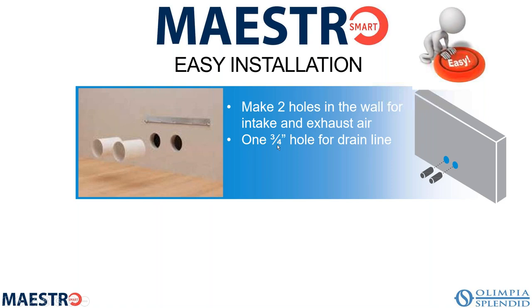So next, after you have cut your holes, now you have to install the duct, okay? So basically the duct has to be installed so that it directs the air into the unit and out of the unit, not into the wall cavity or into the space. So the duct work, and this is the bracket, by the way, that the unit mounts on back here that was put on according to the holes that were in that template, okay? And then the duct you cut to the thickness of the wall. So let's say your wall is 8 inches thick. You would cut the length of your duct about 6.5 inches, so about an inch and a half short of the exterior, and then it goes into the grills and the ring, okay?